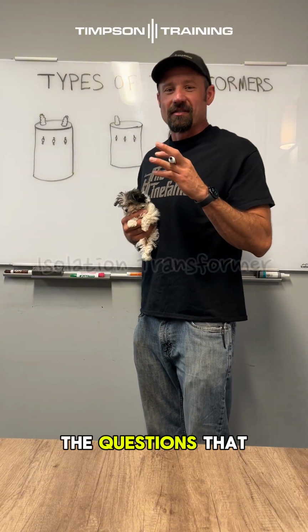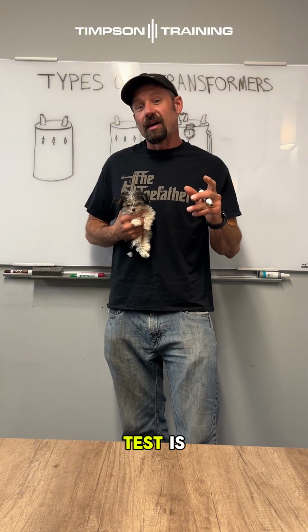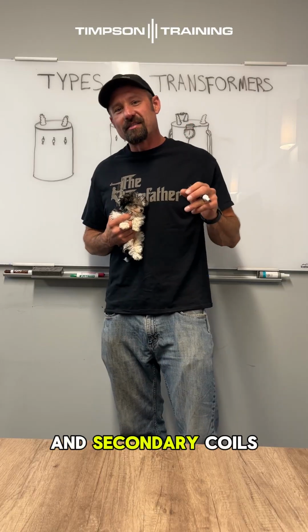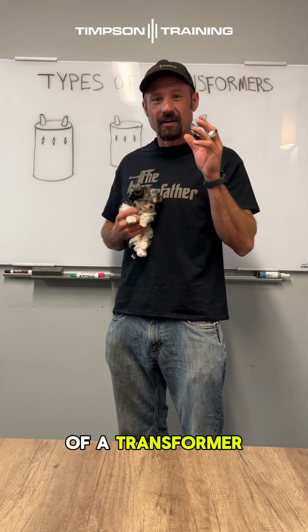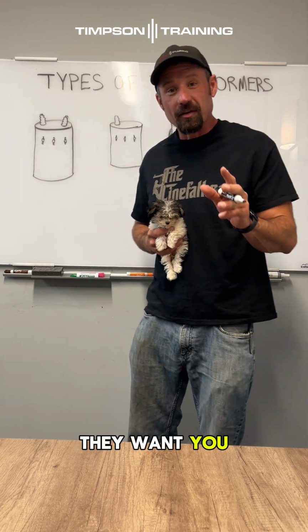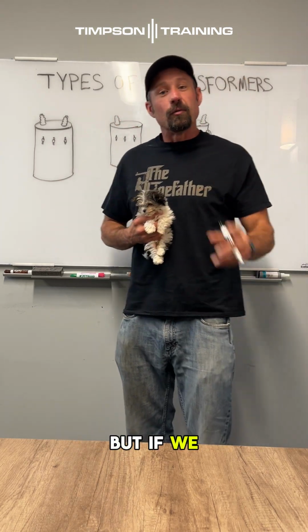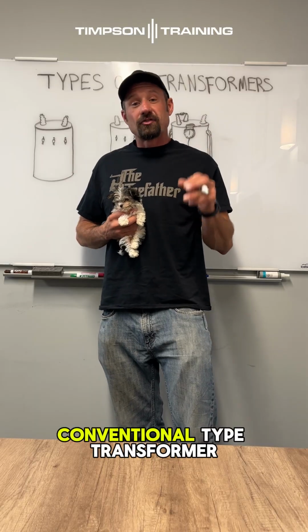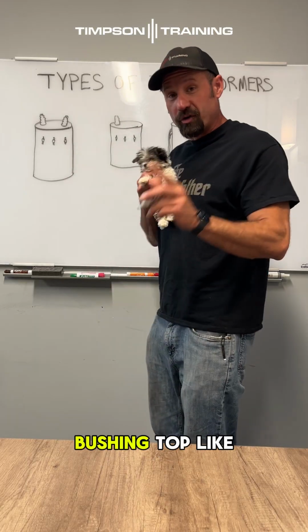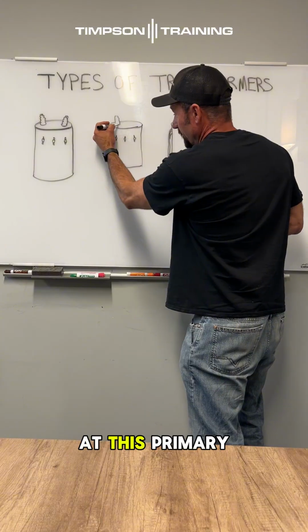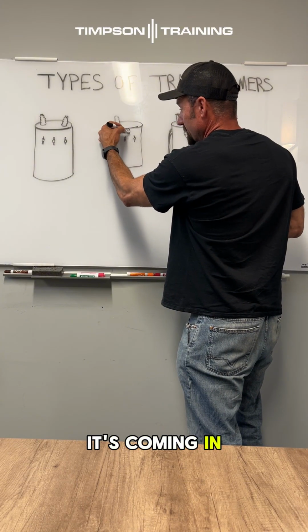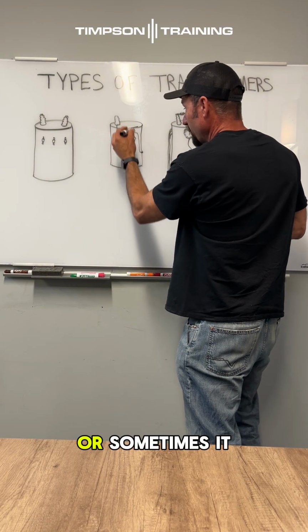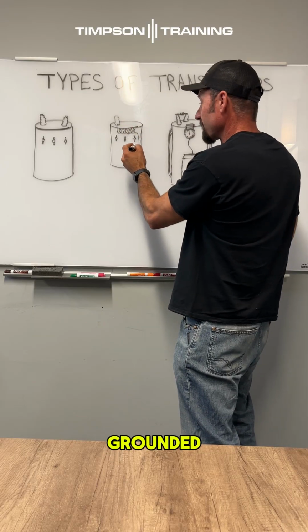And one of the questions that you might get asked at a journeyman test is, are the primary and secondary coils of a transformer electrically connected? Right? And of course, the answer that they want you to say is no. But if we look at a conventional type transformer, say a single bushing top like this one, if we look at this primary coil, it's coming in and it goes out to that little stub, or sometimes it goes to an H2 that gets grounded.